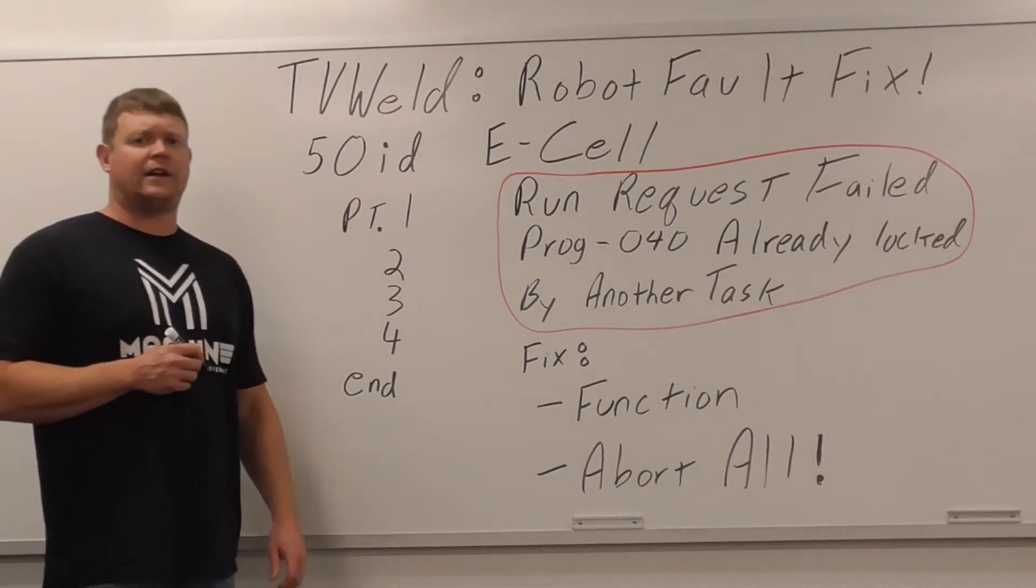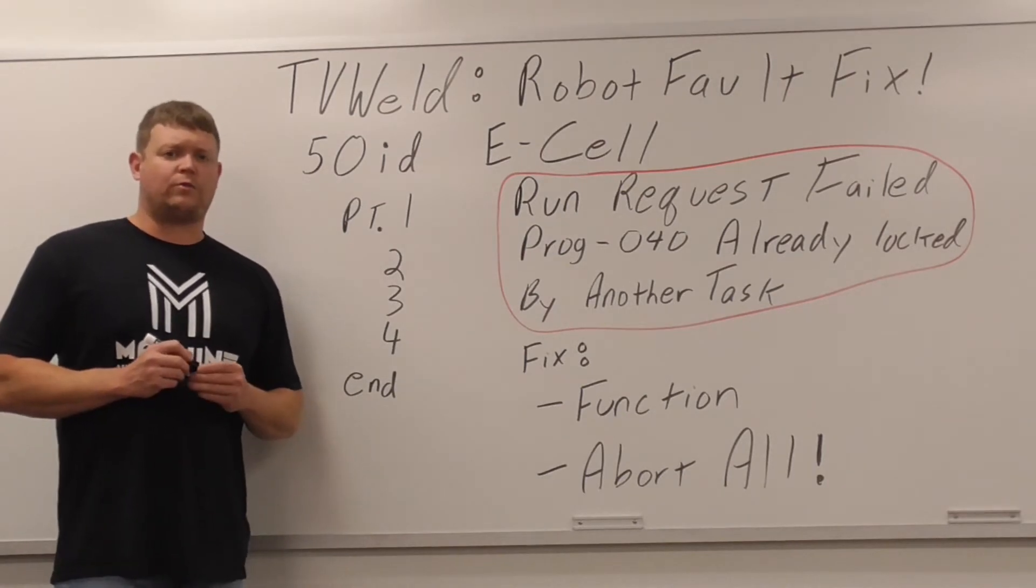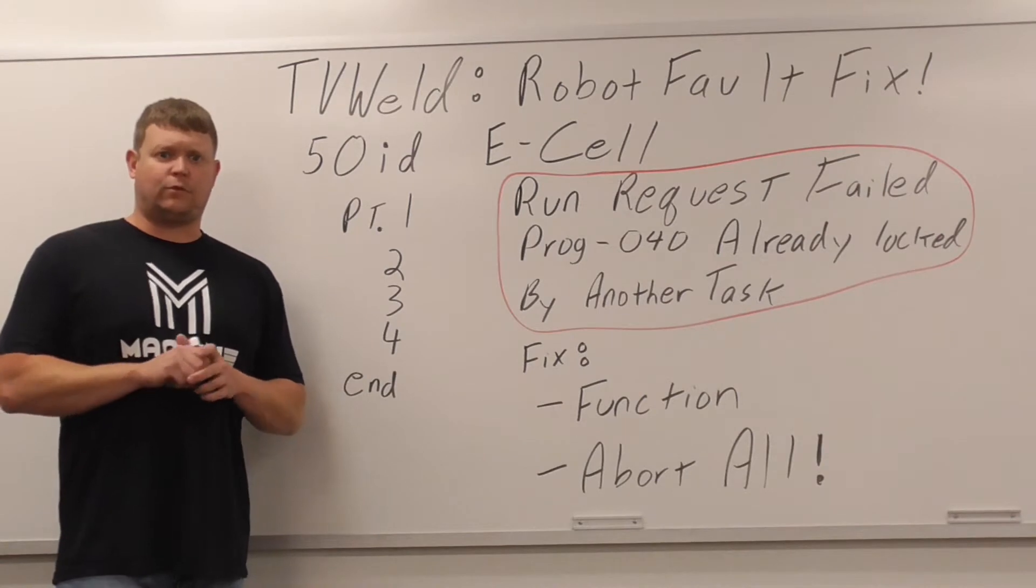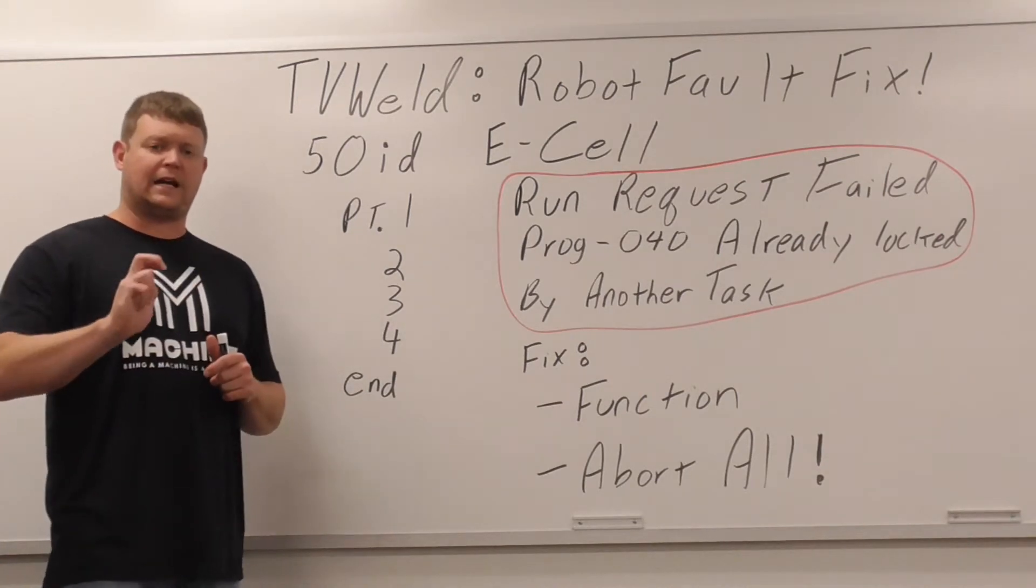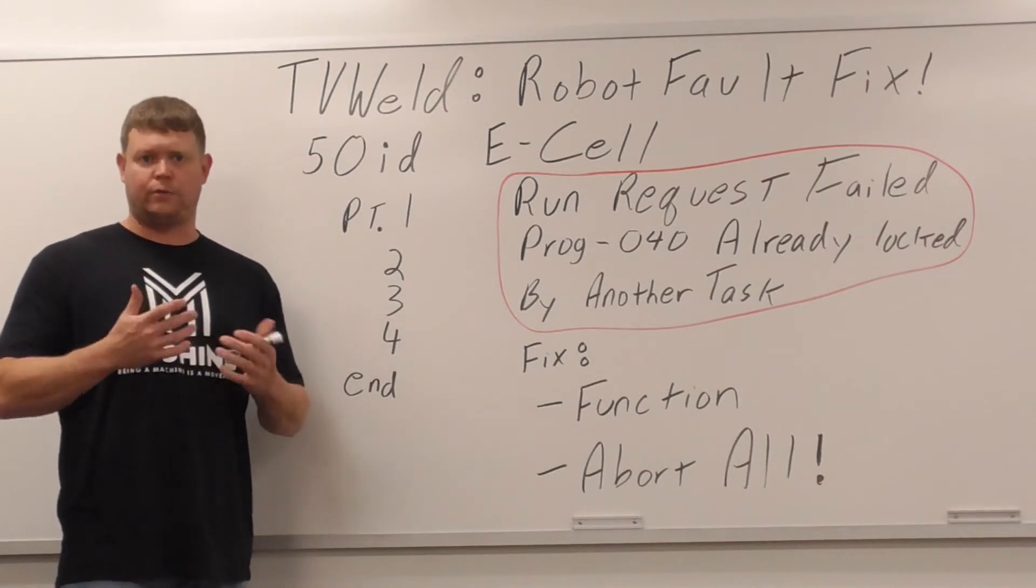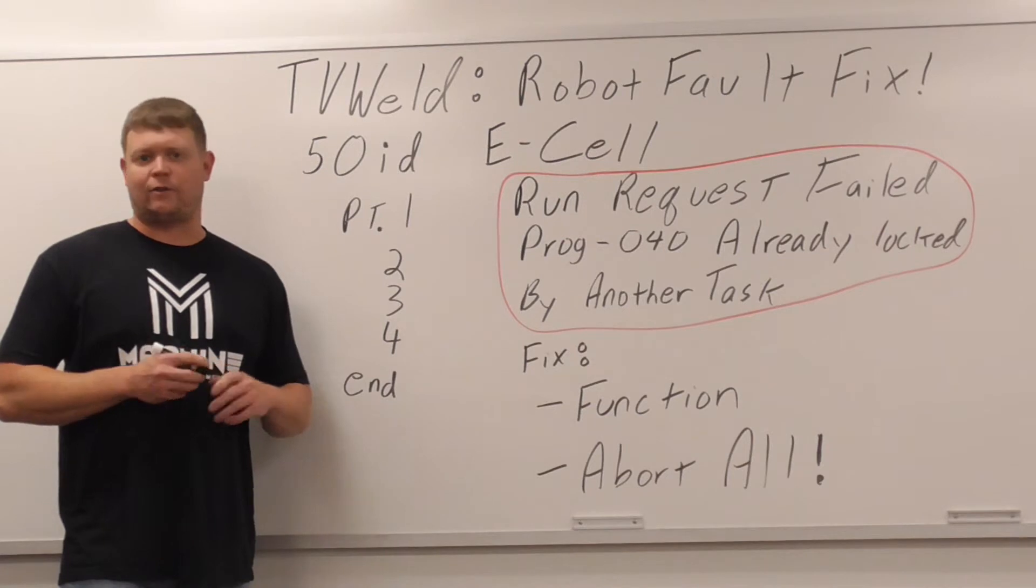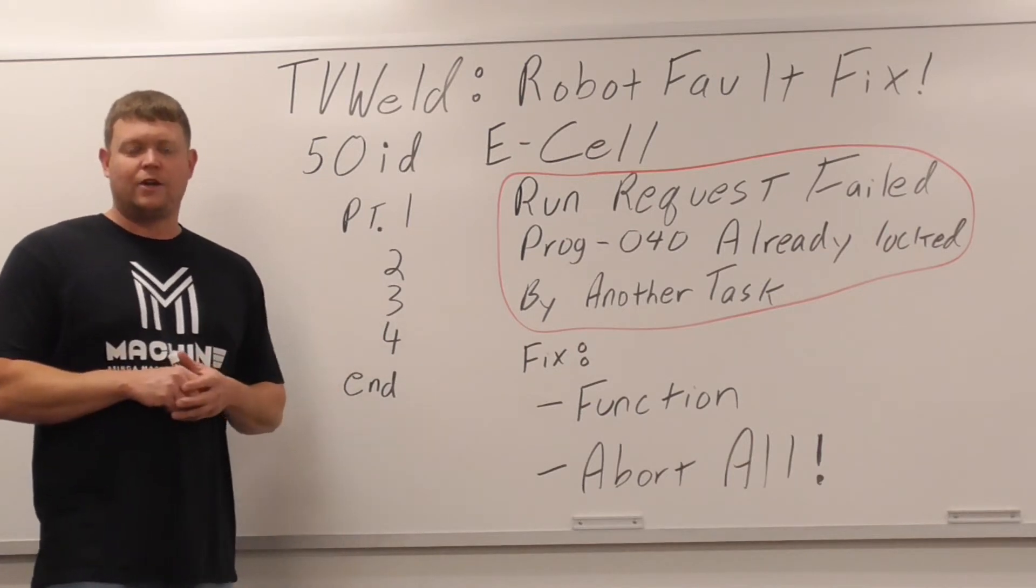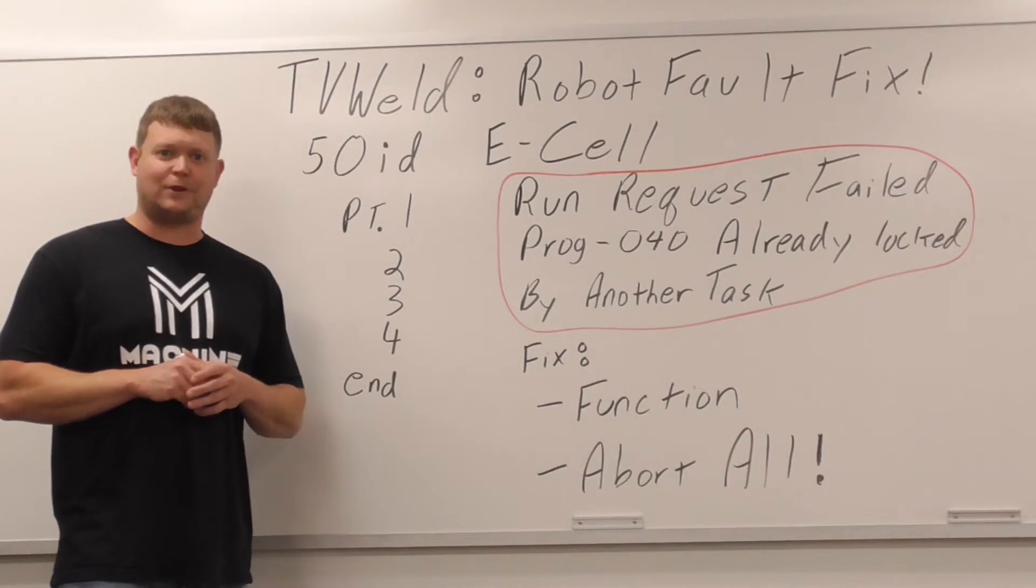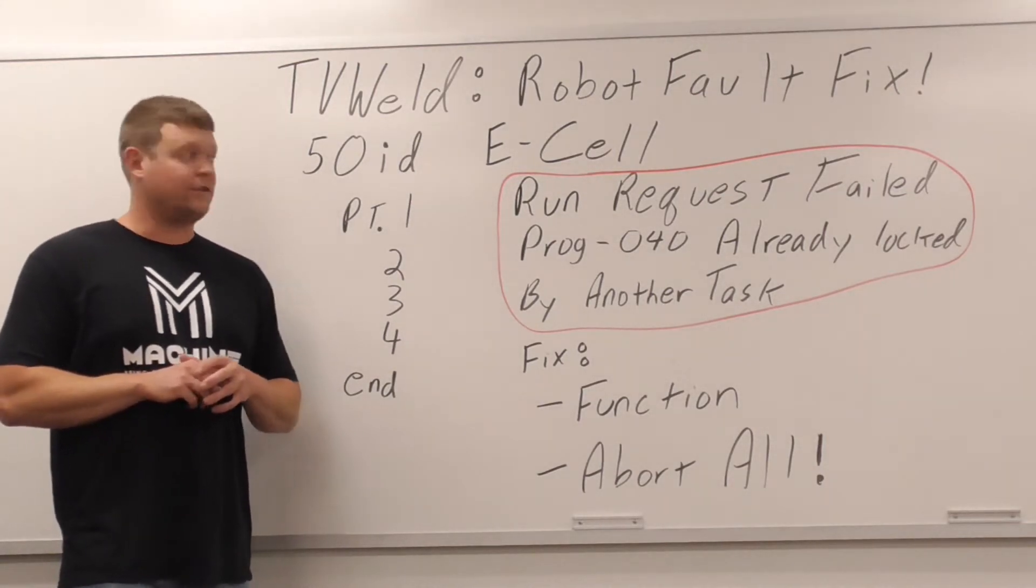It's a very common fault that I get on FANUC. I used to get it all the time on our 100i. I was working with a guy and he was getting the fault and he kept going over and turning the robot off and back on again. That will clear, but then you have to select the program again and wait for it to boot up. I showed him how to fix it the correct way, and he said that's going to save you a lot of time. So I thought I'd shoot a little video on it real quick.